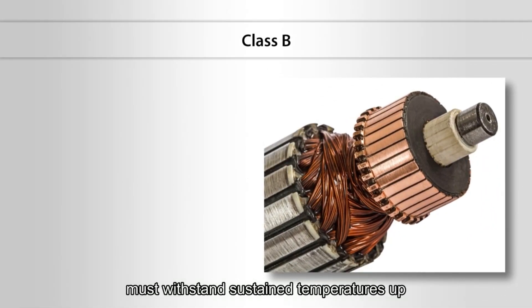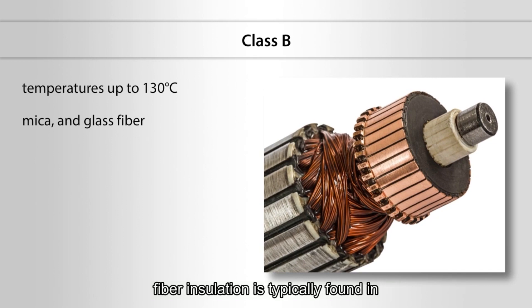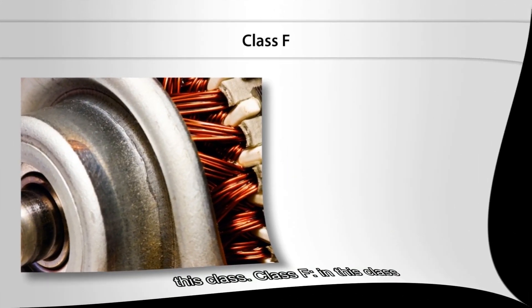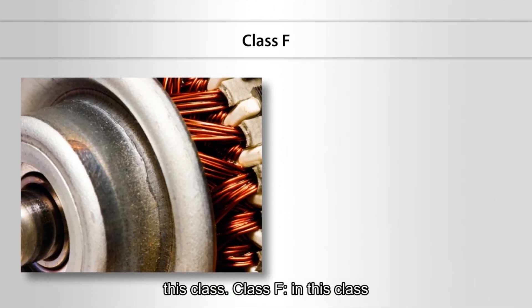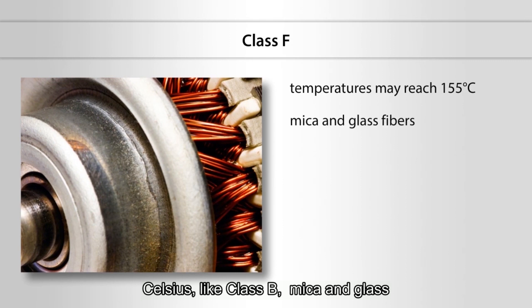Class B insulation: in this class, insulation must withstand sustained temperatures up to 130 degrees Celsius. Mica and glass fiber insulation is typically found in this class. Class F insulation: in this class, temperatures may reach 155 degrees Celsius. Like Class B, mica and glass fibers are used as the insulating medium.